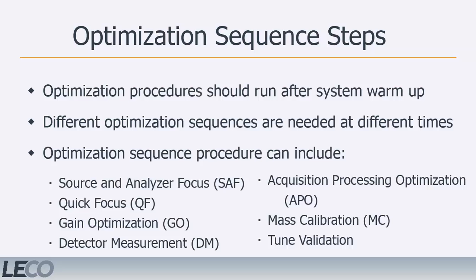Once the Pegasus GC-HRT has been sufficiently warmed up, the user can begin a system optimization sequence. An optimization sequence includes several automatic procedures designed to automatically adjust the various hardware parameters for optimal data acquisition.